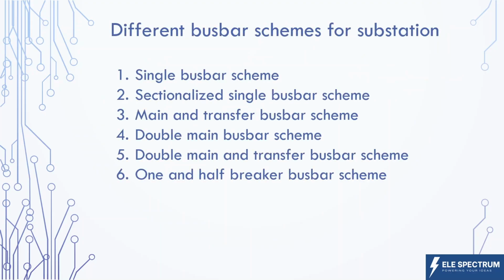So we are going to discuss the most widely used bus bar schemes in substations. And these schemes are single bus bar, sectionalized single bus bar, main and transfer bus bar, double bus bar, double main and transfer bus bar, and last is one and half breaker scheme. So let's start with the first and simplest bus bar scheme, which is single bus bar scheme.